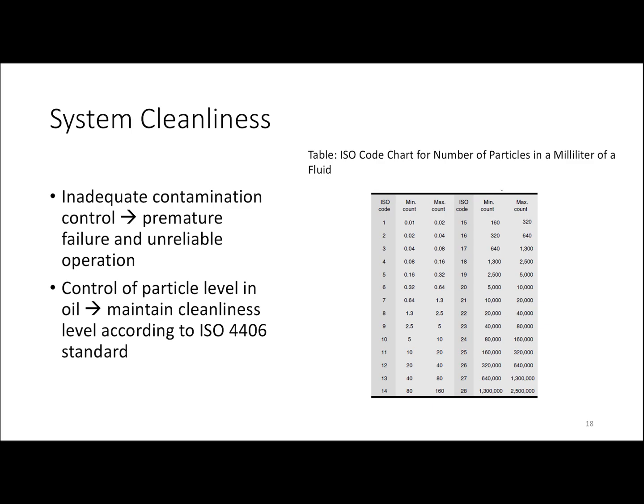That's why the particle level in hydraulic oil must be maintained, which is already regulated by the ISO 4406 standard. For example, ISO already has a chart with codes from ISO code 1 to ISO code 28.